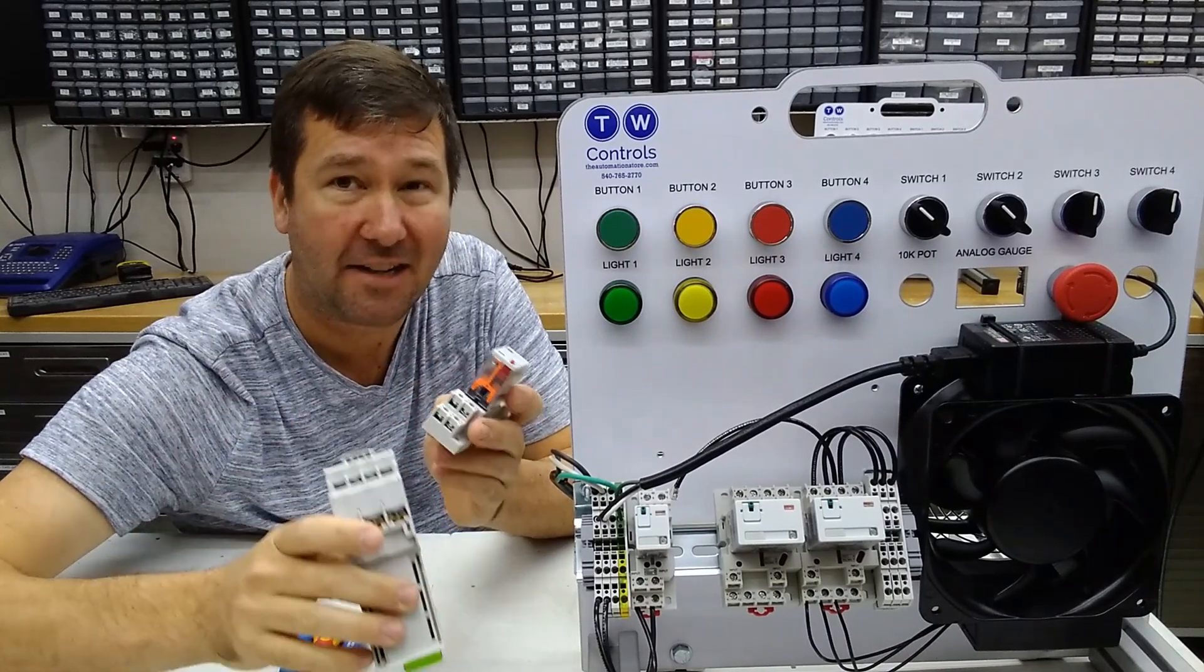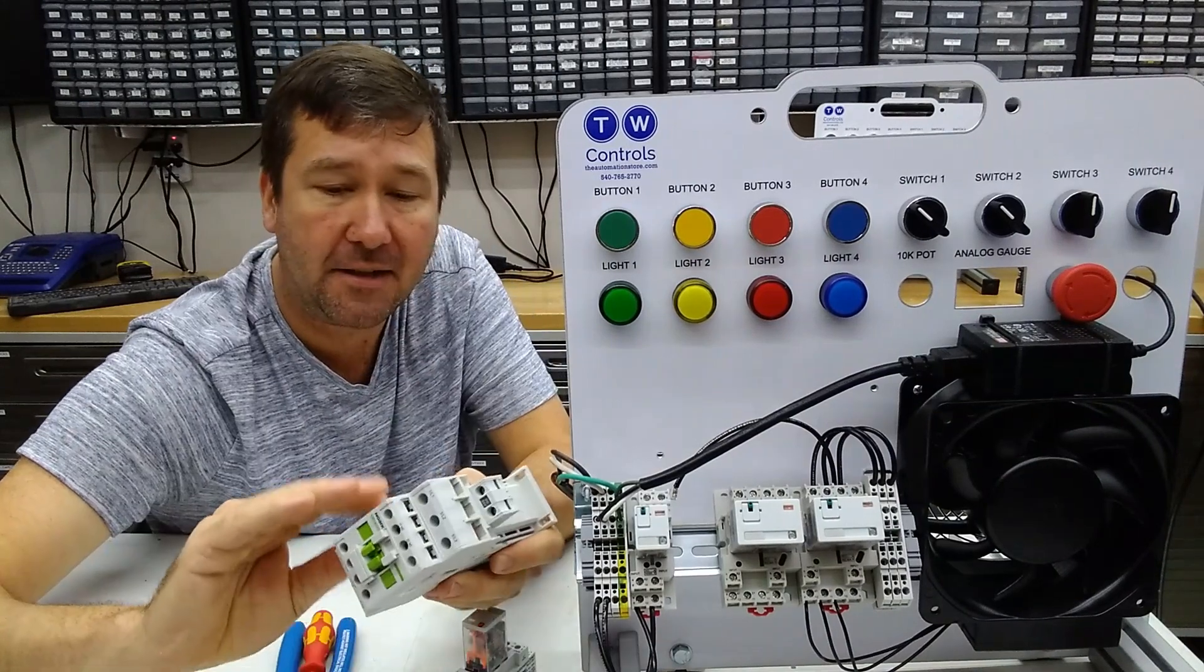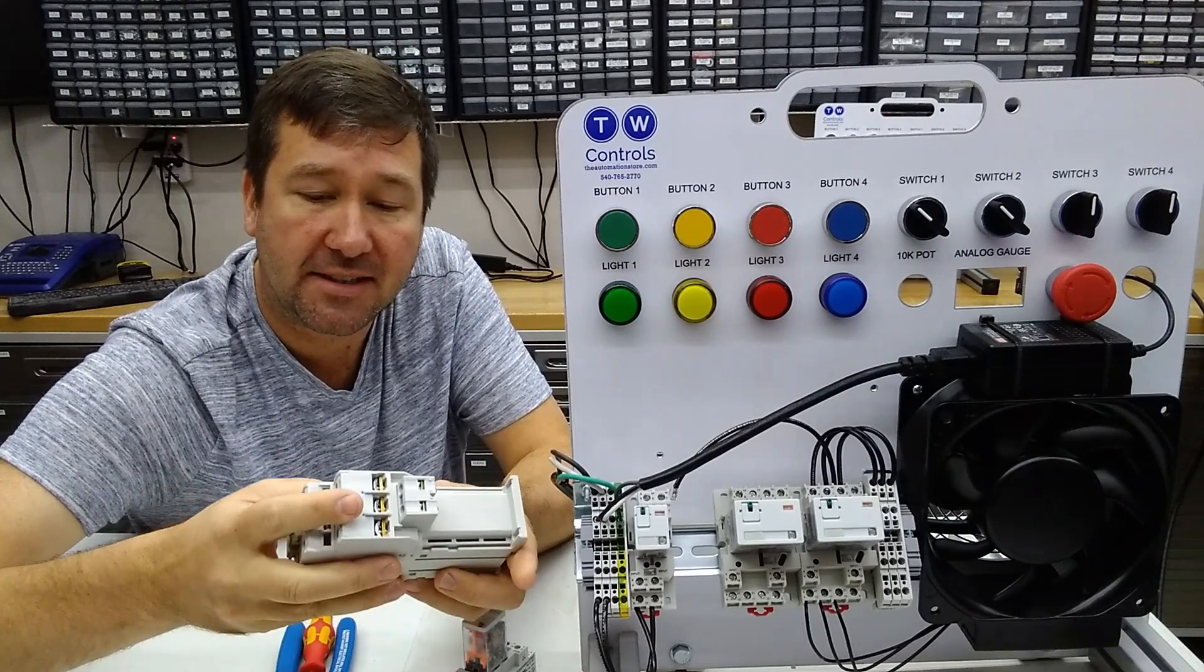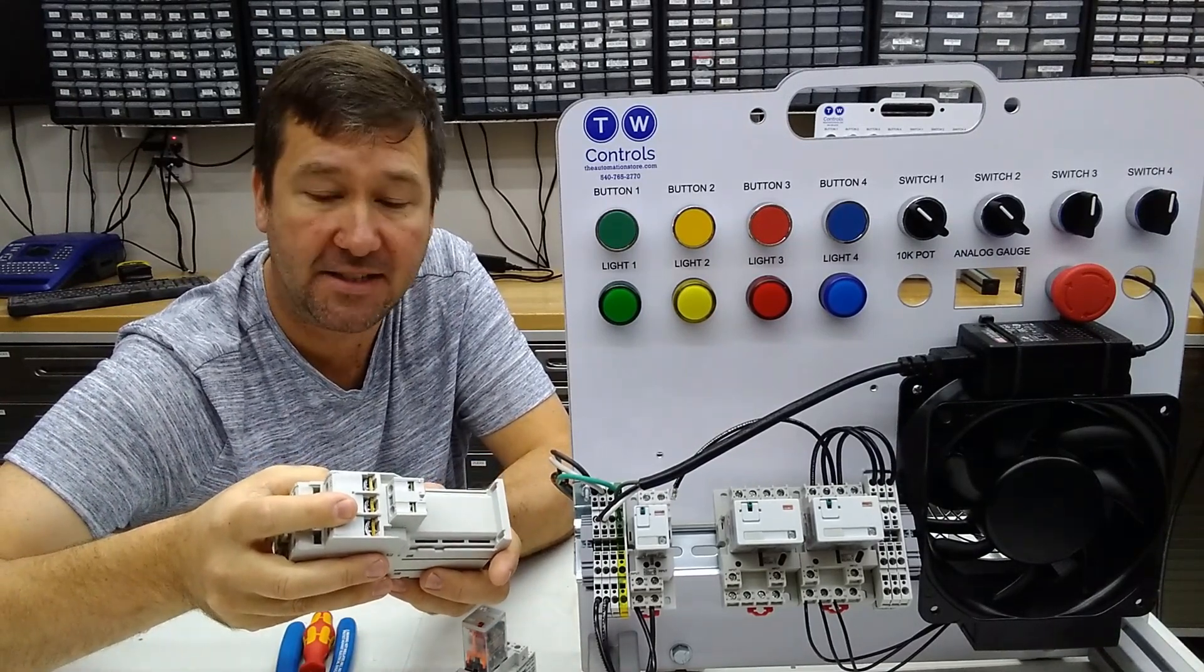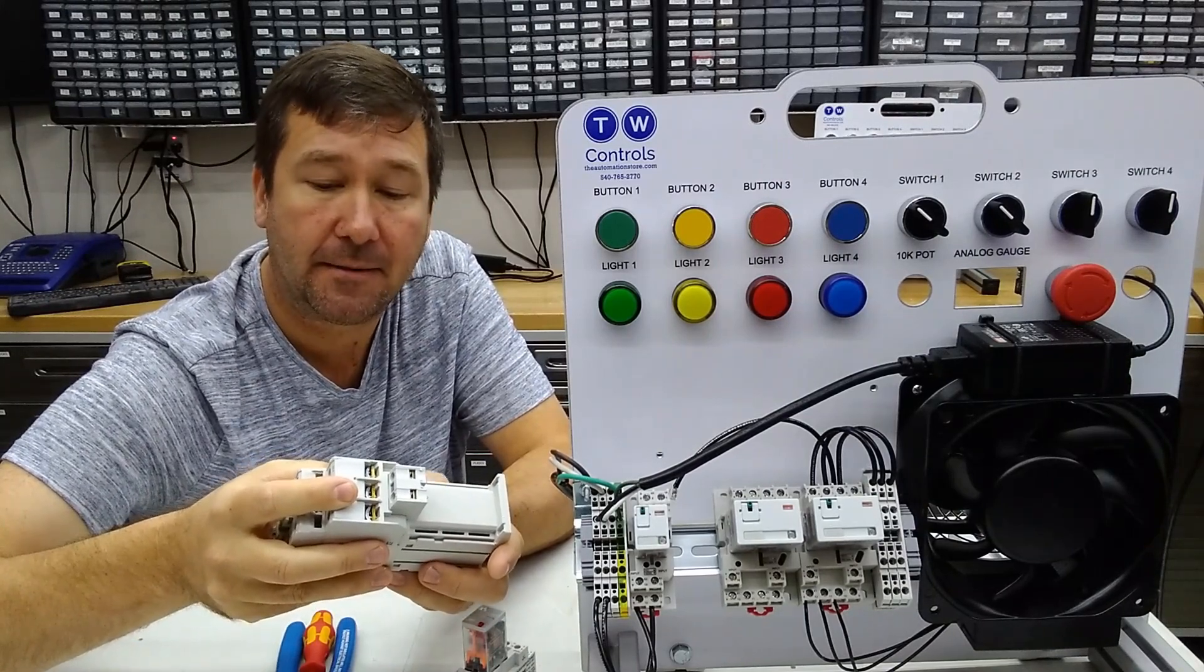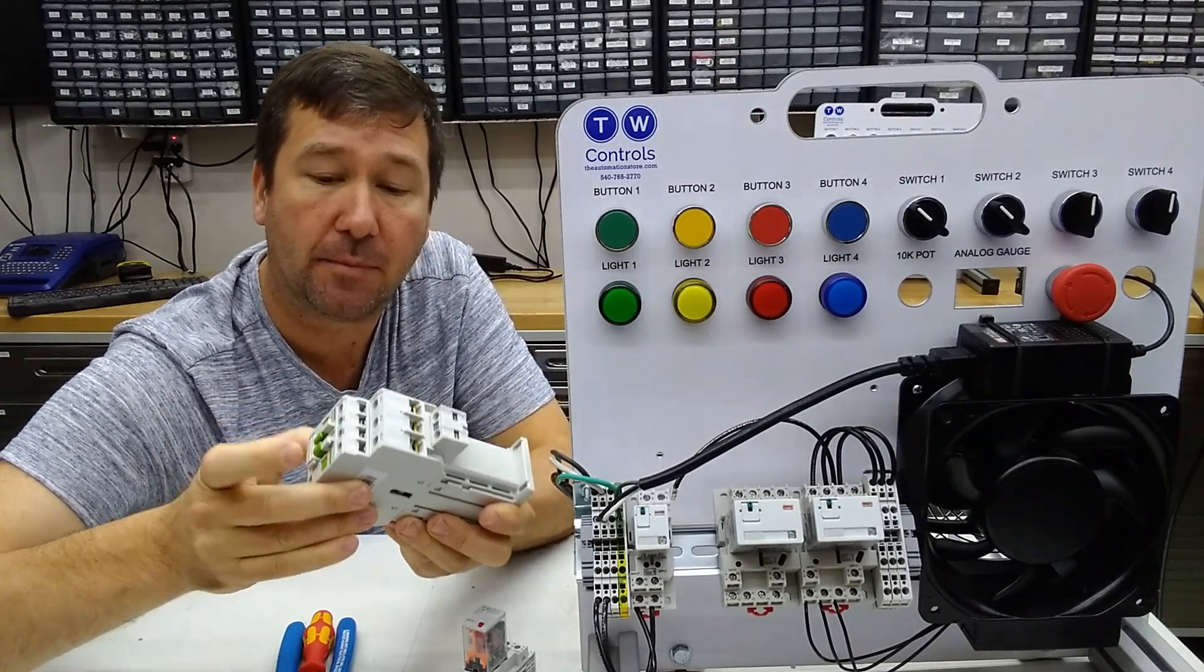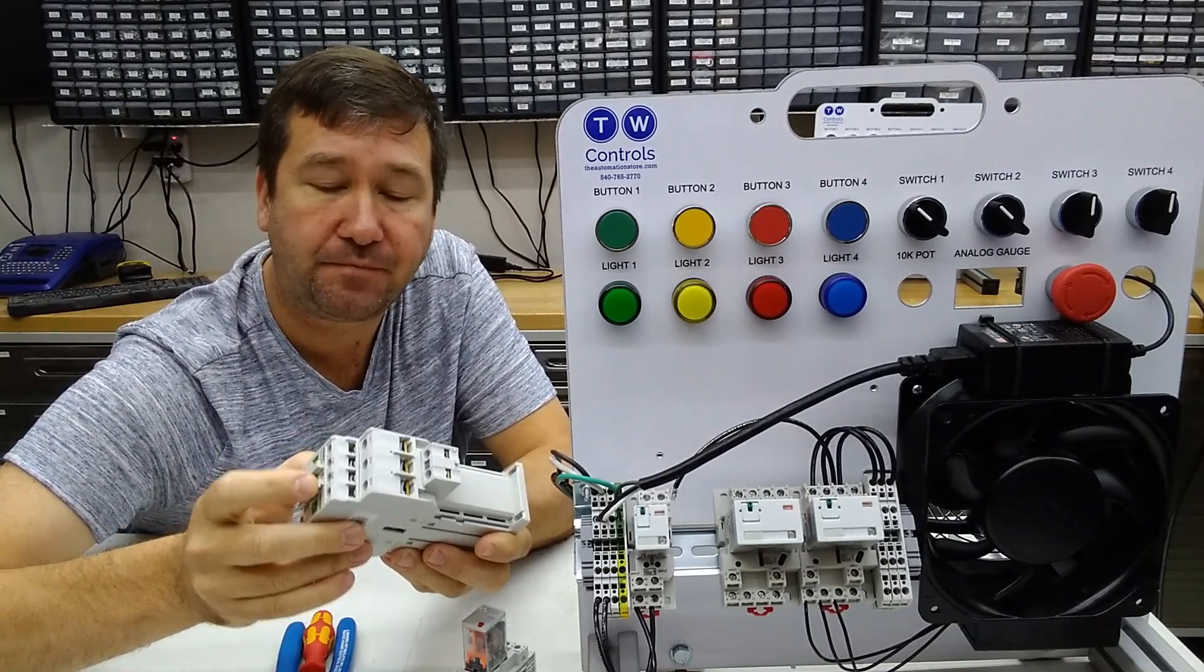Also, contactors and sometimes relays will actually have a horsepower rating on them, and that's an important thing to look at when you are sizing your contactor. If we look at the side of this, it has a chart here with voltage and phases. It has one phase or single phase and three phase. On single phase at 115 volts, this can handle a one and a half horsepower motor. Or at 240 volt on single phase, it can handle a three horsepower motor.